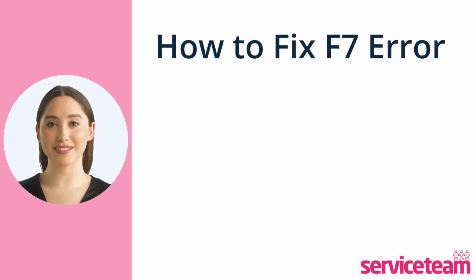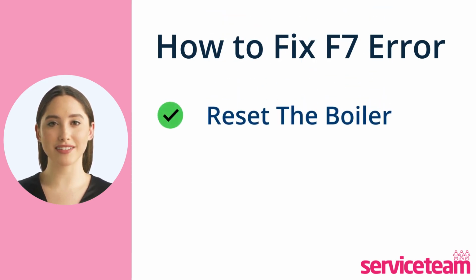Every error code has a solution. So, let's see how to fix the F7 error code. First, we can try this by resetting the boiler. However, the resetting procedure may differ from boiler to boiler, depending on the boiler model. Here's what you might need to do. Turn off the boiler. Wait for the recommended period, as in the boiler manual. Then, reboot the boiler. Remember, dealing with boiler issues requires expertise and technical knowledge.